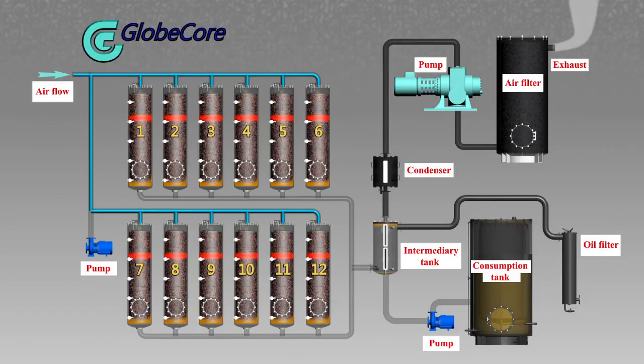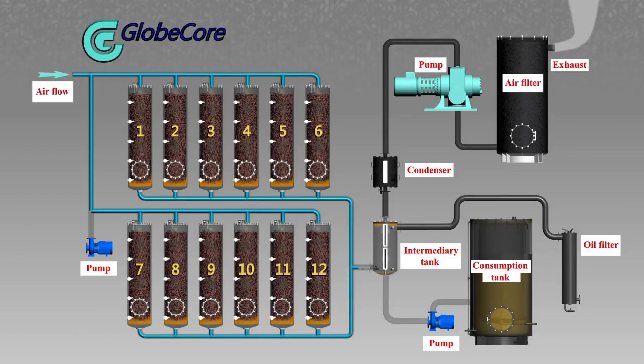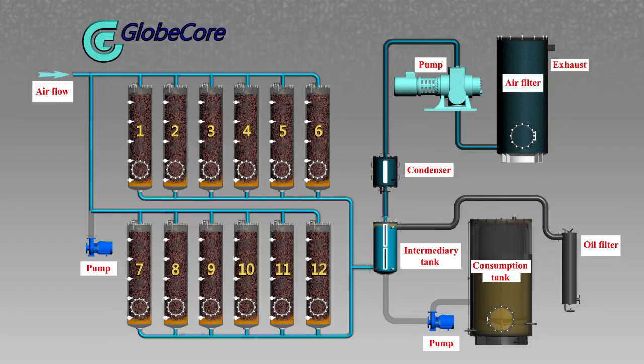The vacuum pump creates the airflow for sorbent reactivation. All oil decomposition products are burned and expelled from the machine after catalytic breakdown into safe, non-hazardous compounds. Reactivation lasts until the sorbent cools down entirely, which is indicated by cold air in the exhaust system. After reactivation, the control system refills the system from the consumption tank and switches the unit into oil regeneration mode. During sorbent reactivation, the degasser continues to process the oil. Regeneration machines can be operated continuously — the only difference with a regular machine is an additional bank of sorbent columns.